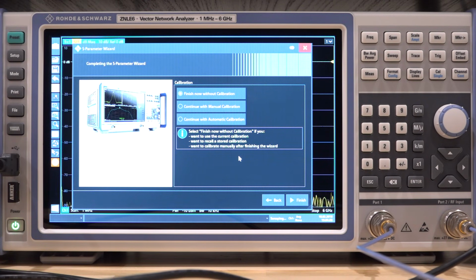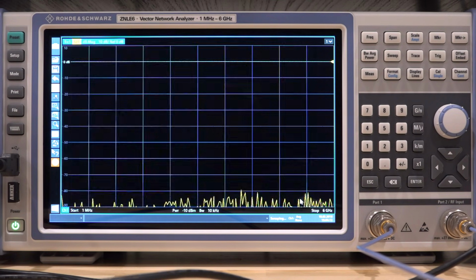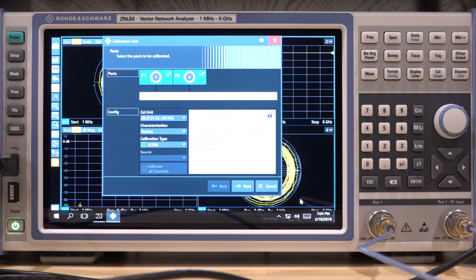So now we're done with setting up the instrument. Now it's asking us, do you want to calibrate or you want to skip that? Well, obviously I want to do a calibration, and we're going to do an automatic calibration because we have an auto cal already connected to it. Let's go finish over here. Now we're going to get the menu for the automatic calibration. Now here we have the cal unit detected. Characterization, we're going to use the factory, which is a female SMA on both terminals of the calibration unit, and that's exactly what we have.